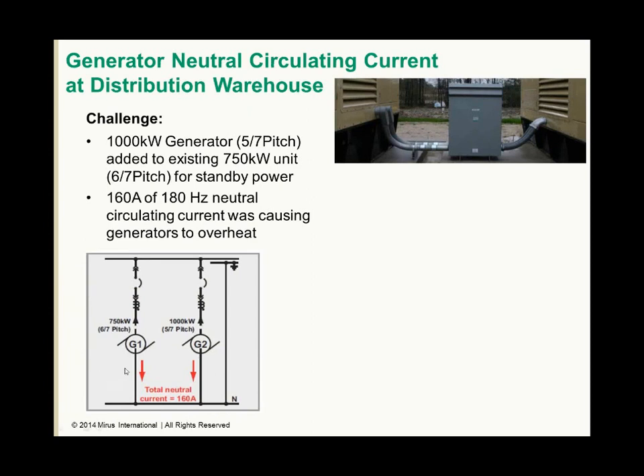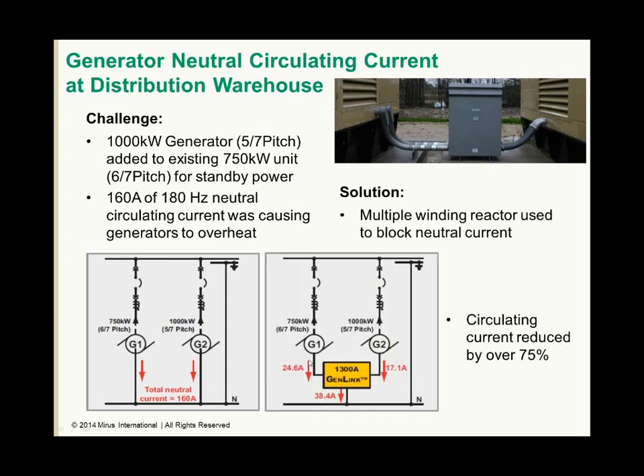So you can see here the two generators. There's our shared neutral. They had 160 amps of neutral current at 180 hertz circulating through the system. A very unique neutral blocking reactor, referred to as GenLink, was installed in the neutral between the two generators and reduced the circulating current. So we now had from 160 amps down to 38.4 amps. And you can see the current coming in from generator 1 and coming in from generator 2.